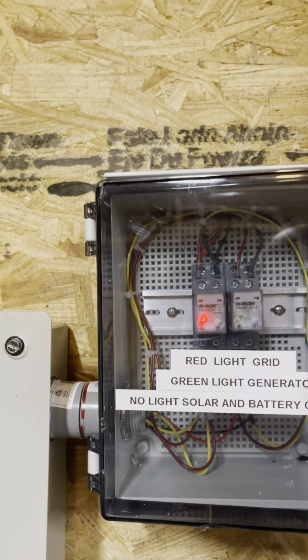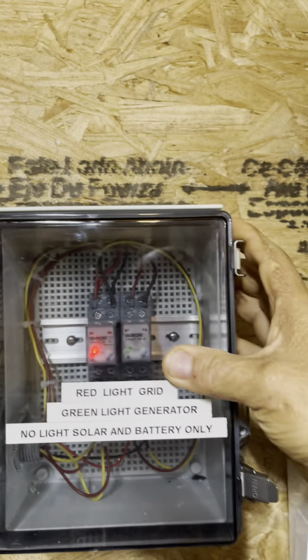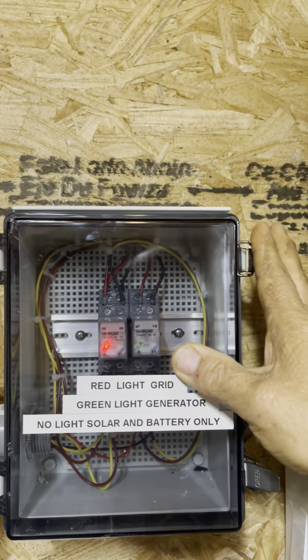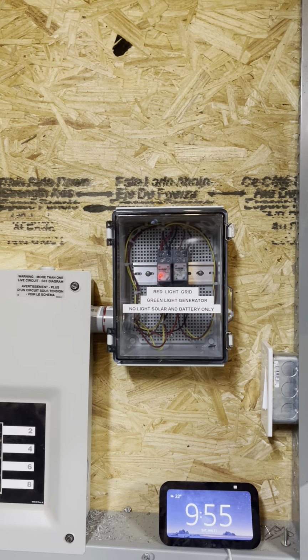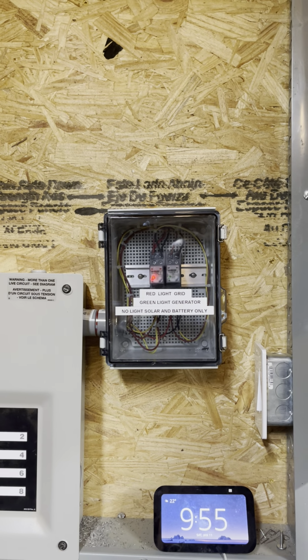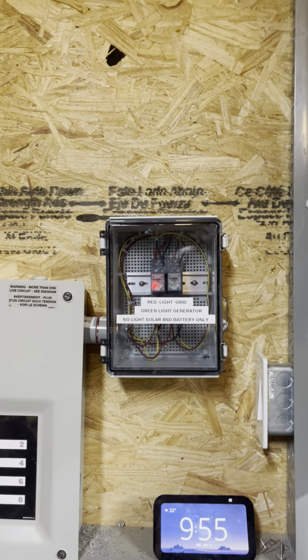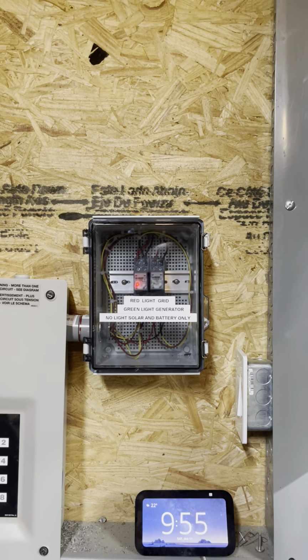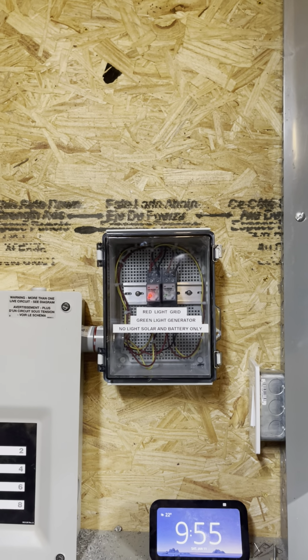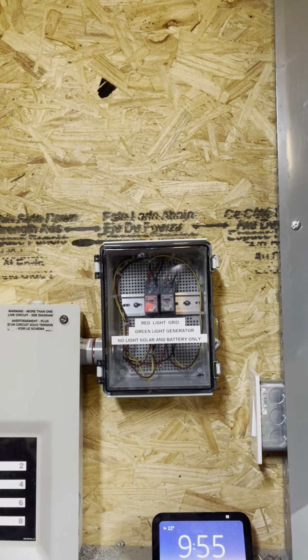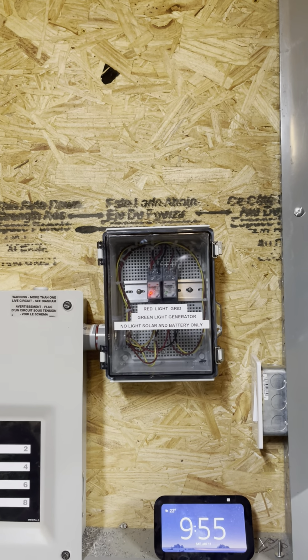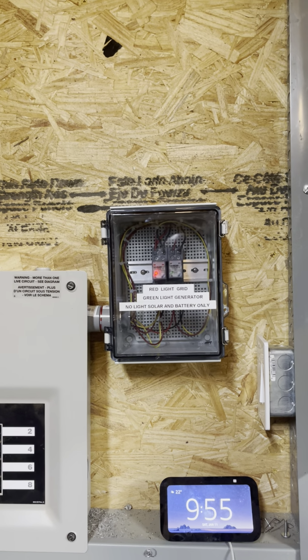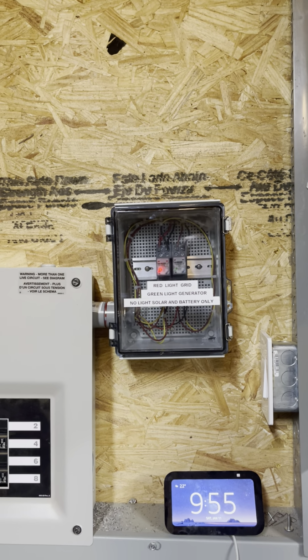And there the generator fired off. And I'm going to close this panel up because, like I said, it does have both 12 volts and 240 volts in this. But the red light signifies that the main power is back on, and it's nice because you can see it from across the room. The red, the green, or both, or none. If by some chance the batteries were full when we lost power, and the inverter sensed it didn't need to start the generator, you would have no lights because you'd be running off battery and solar panels and PV. So that way the PV is going to do its job and use as much solar as you can before you require the generator to kick in.